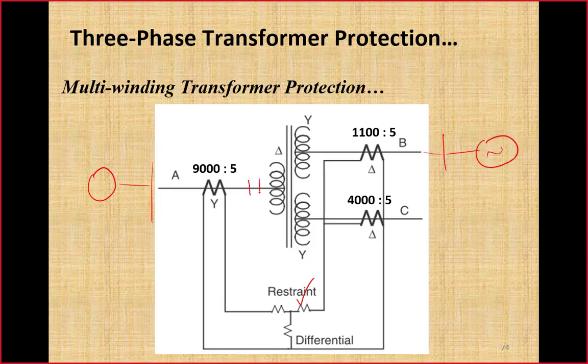If it is open circuit here at winding A side, only winding B and C are in service, means it is providing to the load like this. So power was flowing from winding B into winding C. Definitely power rating of this transformer in this mode could not be more than 200 MVA.